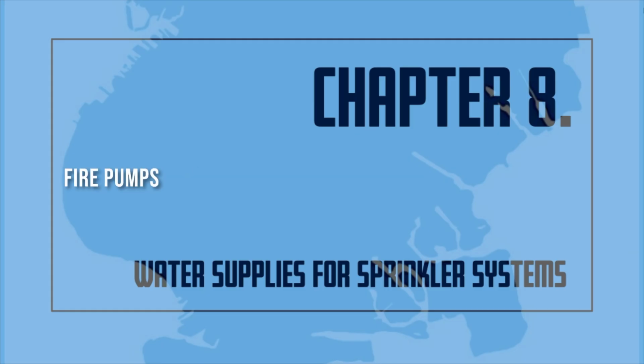Fire pumps. Fire pumps can be used as a main water supply source for sprinkler systems. They may also be used in combination with gravity tanks to supply sprinkler systems. Fire pumps are designed to take the water from a supply source and then discharge the water into the fire protection system under pressure. The amount of pressure with which the water is discharged from the pump is called the total head. The total head is measured in pounds per square inch. The higher the PSI rating of the pump, the greater the pressure with which the water can be discharged.